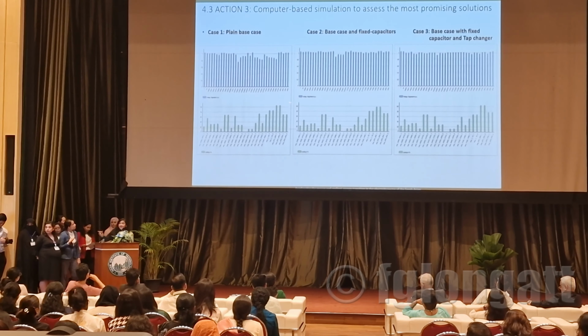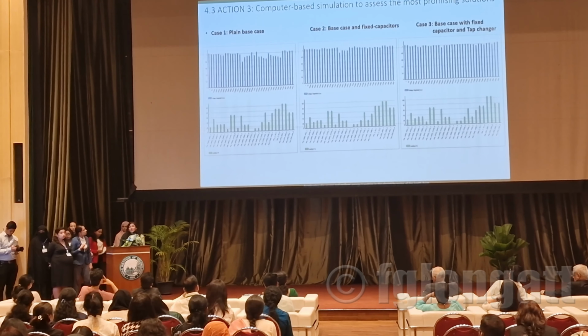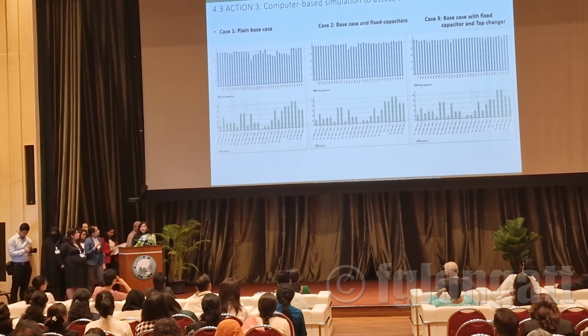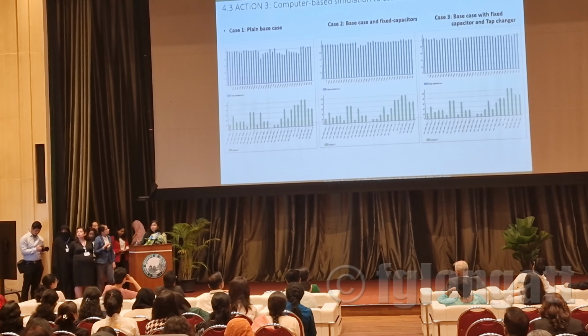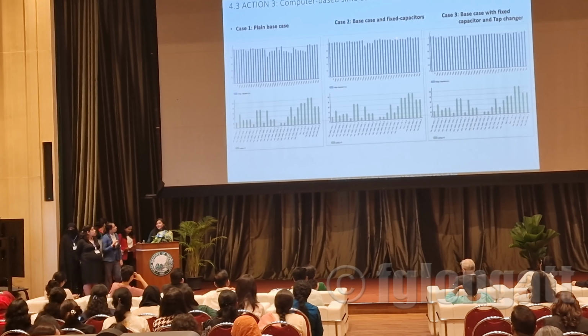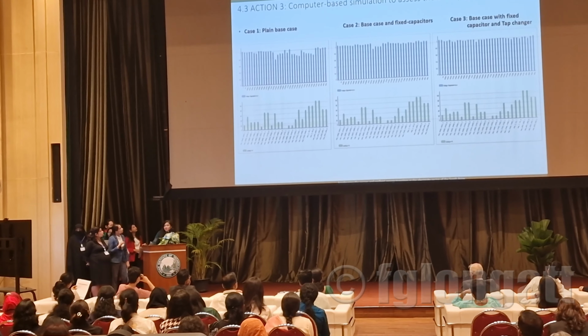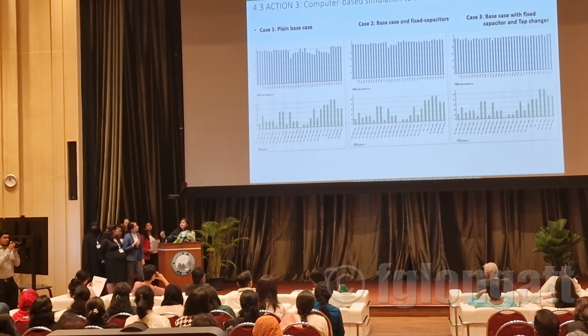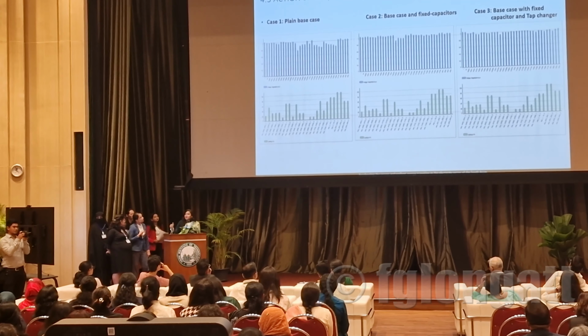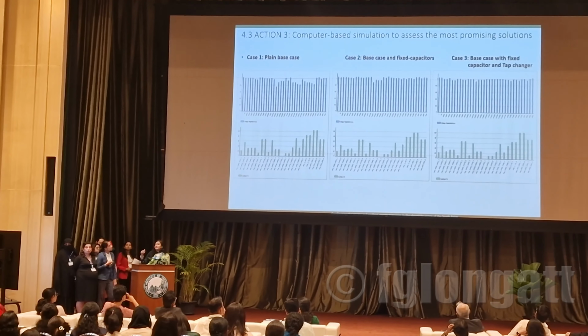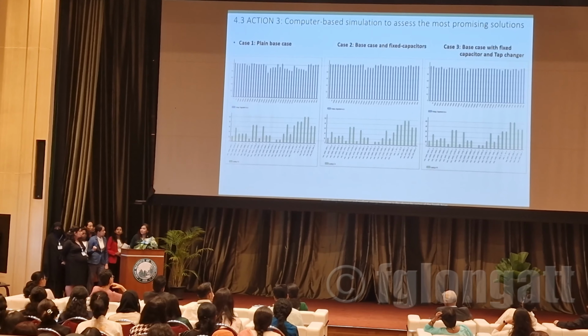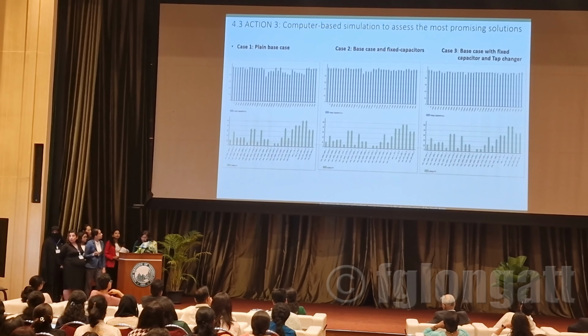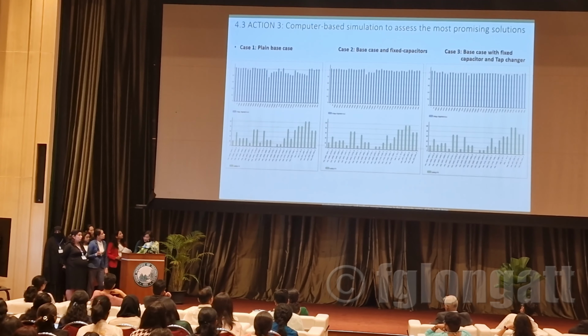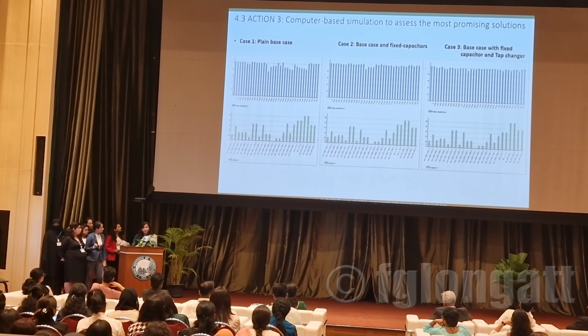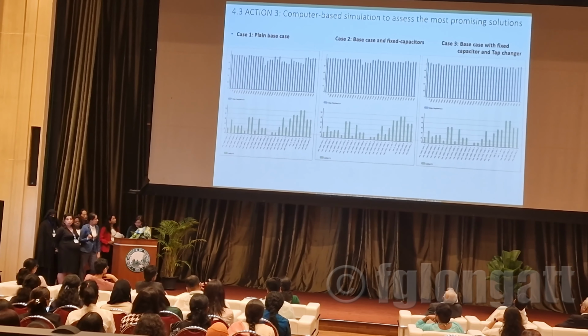In the second case, we fixed capacitors through reactive power compensation, which improved some voltage profiles. In the third case, we also performed reactive power compensation along with tap changing of the transformer position, which further reduced the maximum limit. In the second case, the lower limit is adjustable but the upper limit remains higher, in the limited area. From these 3 cases, we took case number 3 forward for further simulation in our study-based project.